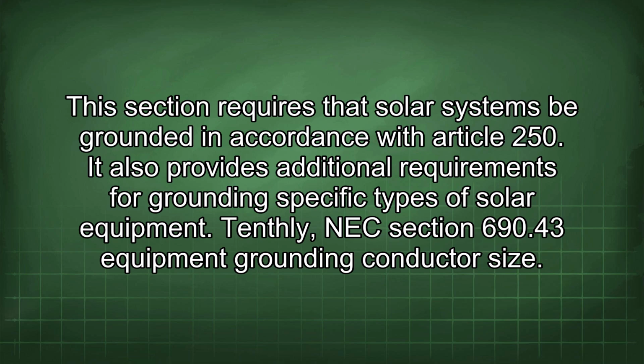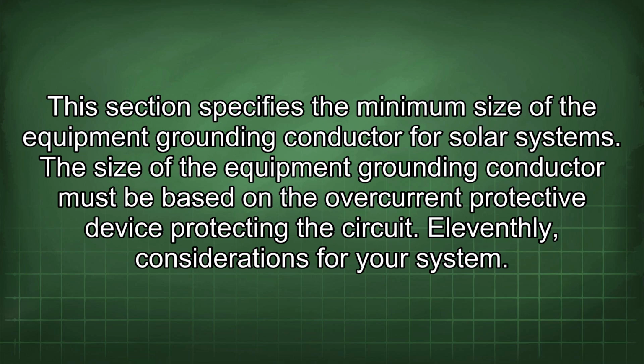Tenthly, NEC Section 690.43 Equipment Grounding Conductor Size. This section specifies the minimum size of the equipment grounding conductor for solar systems. The size of the equipment grounding conductor must be based on the overcurrent protective device protecting the circuit.